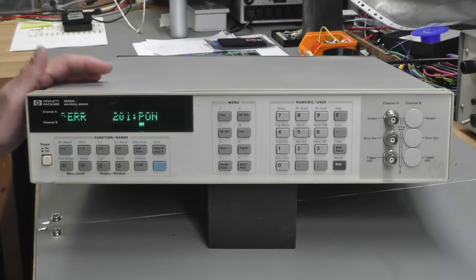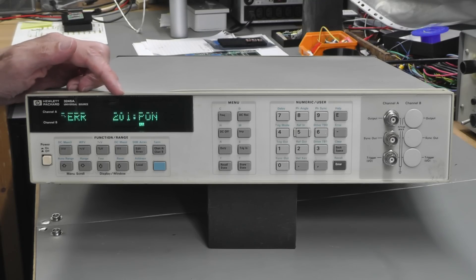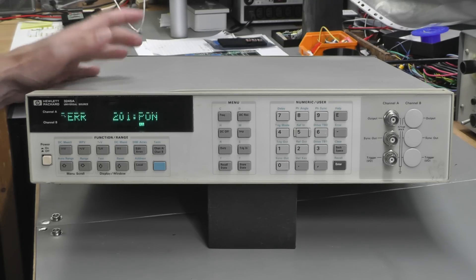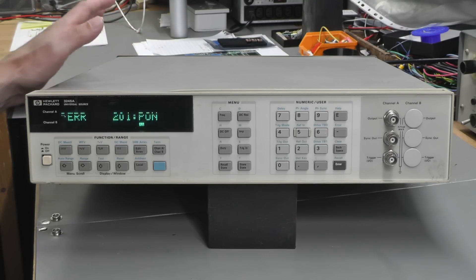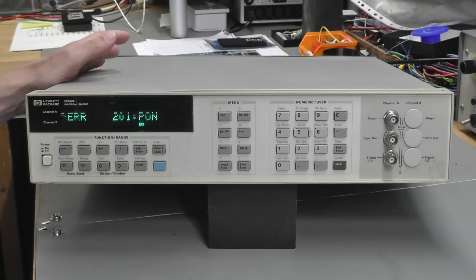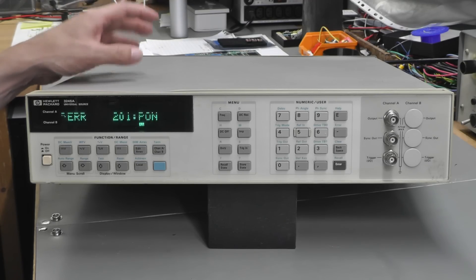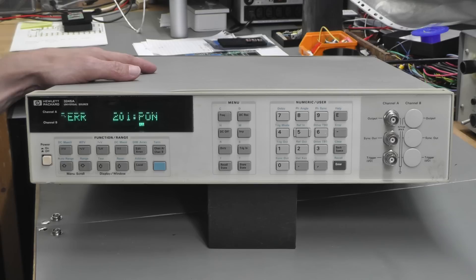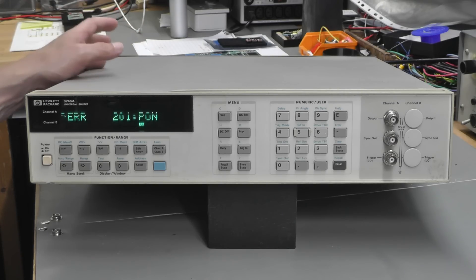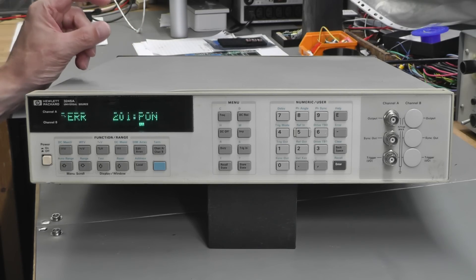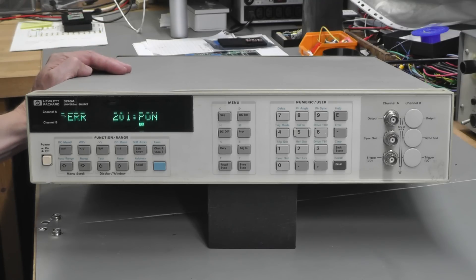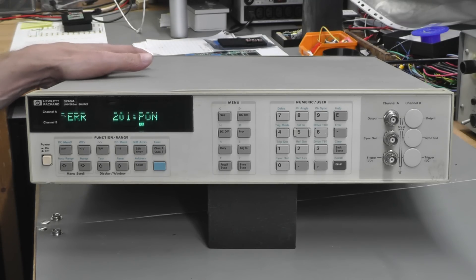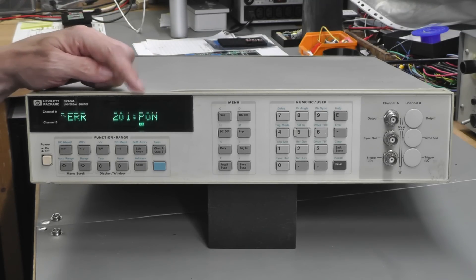Channel A only, that's fine. An error 201 PON. Okay, so the bad CMOS, that's bound to be a problem with the Dallas battery-backed RAMs that are fitted to these units. They do have a shelf life—the batteries eventually go flat. They're encapsulated RAM chips with the battery on the top.